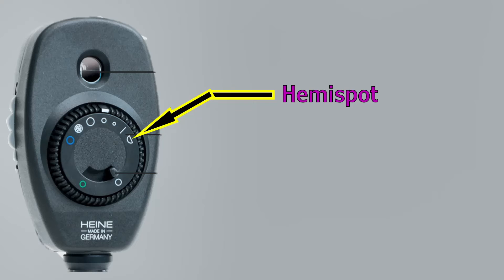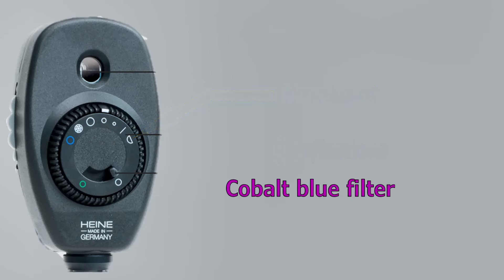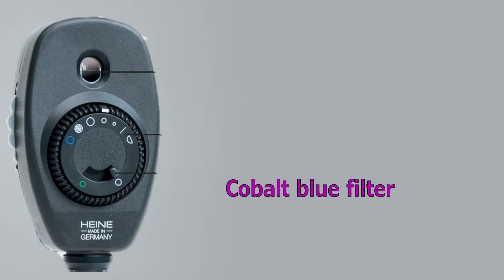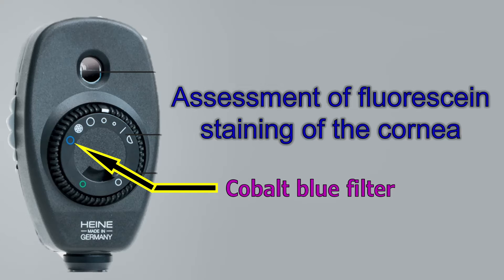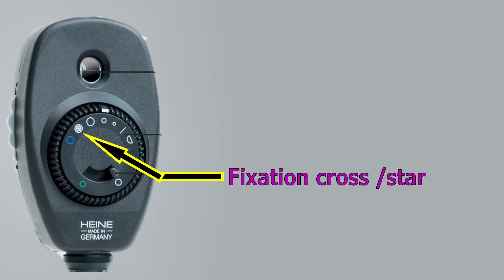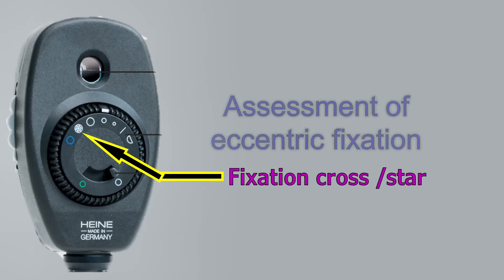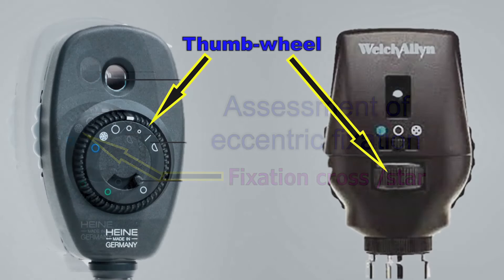A hemispot that reduces reflections, a cobalt blue filter to help in assessment of fluorescent staining of the cornea, and finally a fixation star that projects a graticule onto the retina for assessment of eccentric fixation. These are all available via a thumb wheel.